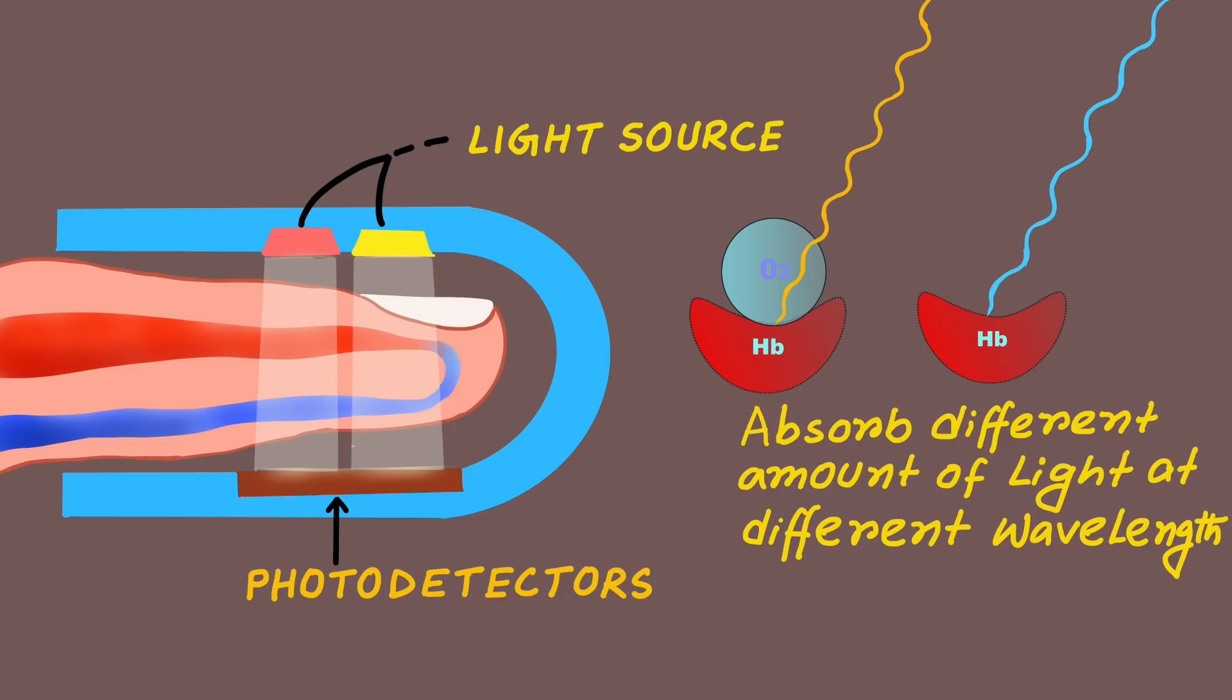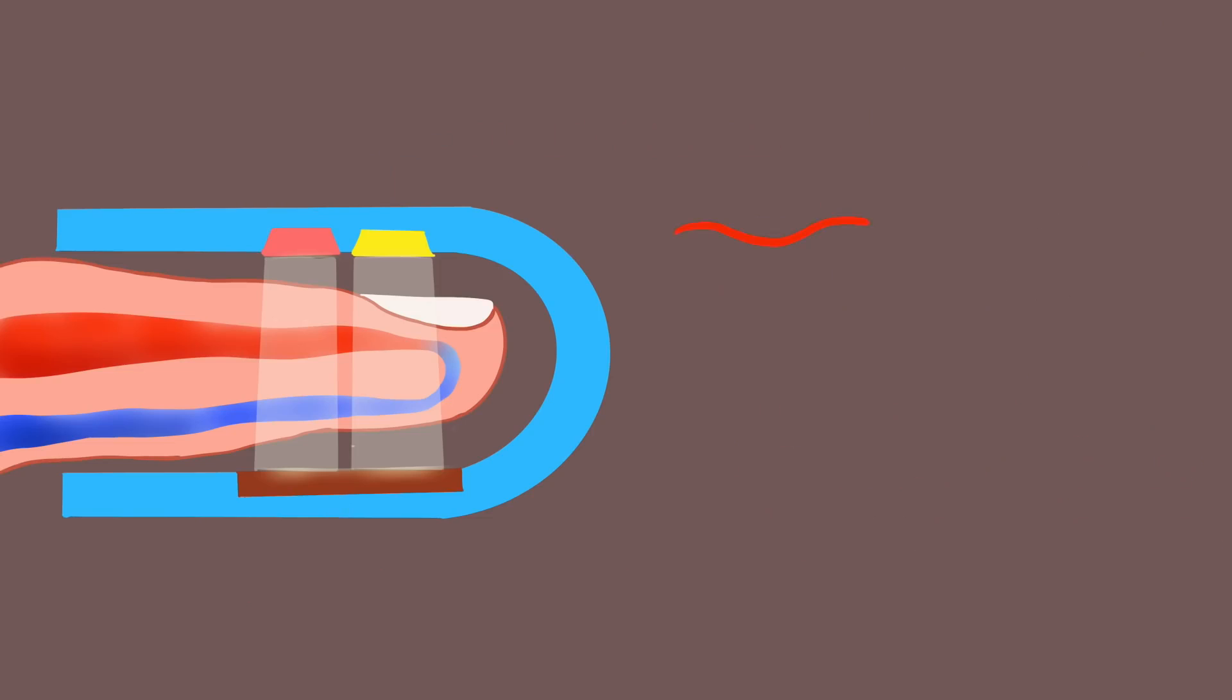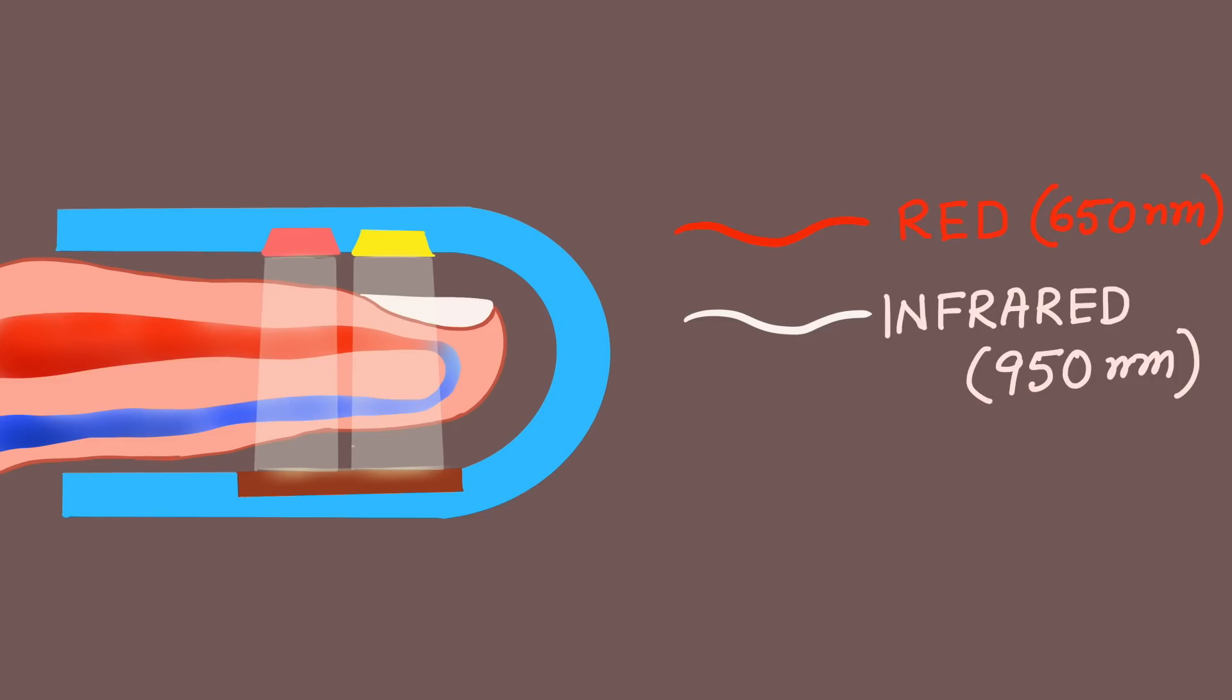Now pulse oximeter emits two types of lights. One is red light which has a wavelength of approximately 650 nanometers and the other is infrared light which has a wavelength of 950 nanometers.